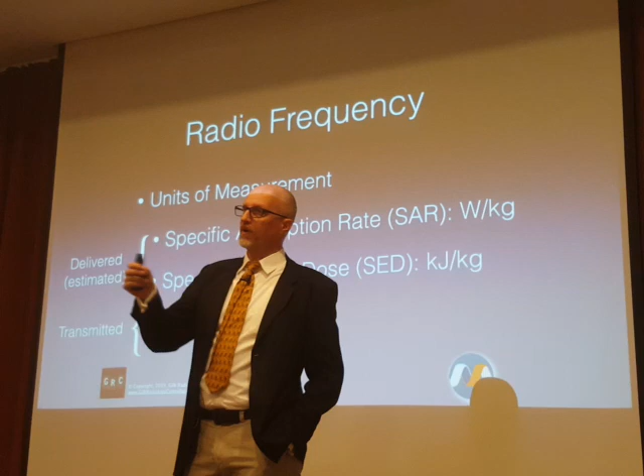Some of your systems may have lockouts. There was, for a period of about 2 years, a requirement that manufacturers limit the total amount of RF energy to 14.4 kilojoules per kilogram for a patient. There are systems out there still today where, if you are doing a total spine on your patient, you may get halfway through the lumbar and it may lock you out and say, I'm sorry, you can't continue. That hardware requirement went away a couple of years ago, but the system software from that era may still have the lockout built into it. It is now up to the individual MR manufacturer to decide if and when they want to have a lockout. So this is our estimated transmitted power, either the rate at which we're transmitting it or the total accumulated transmission. That's how much we think has gone into the body of the patient.